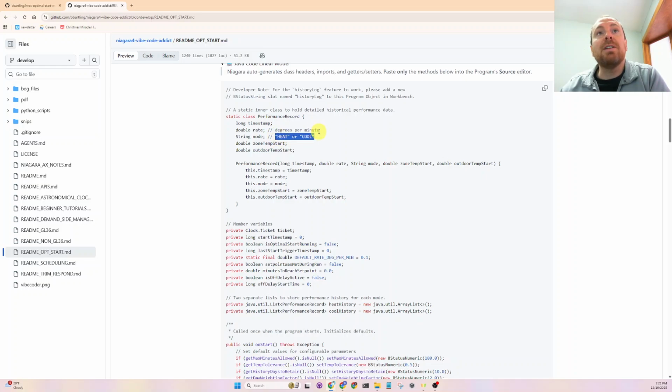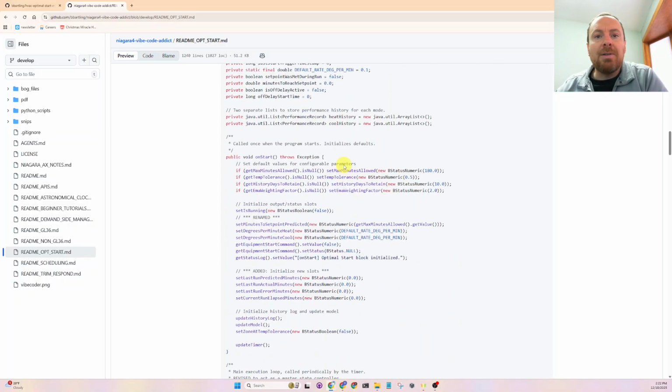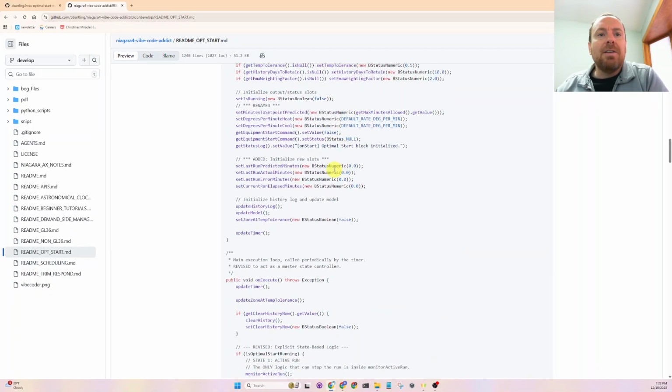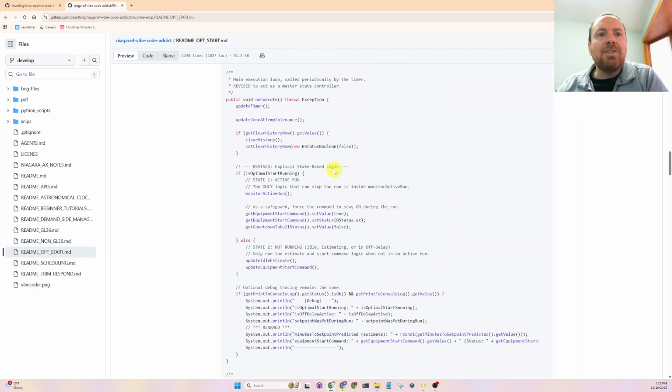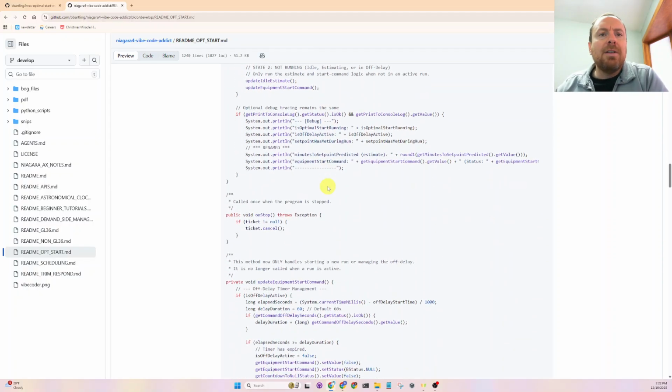So degree per minute will save a separate degree per minute for heating, a separate degree per minute for cooling. And it's all based off of if the zone is recovering for cooling or for heat. And those rates can be different. That's more of the mechanical engineering forte, that the degree per minute data is different because the load calculations are different for heating and cooling.